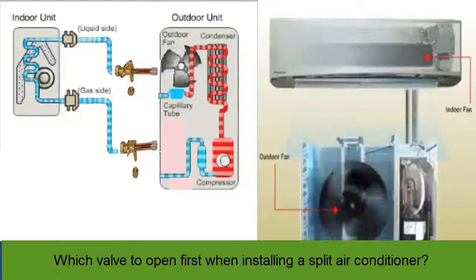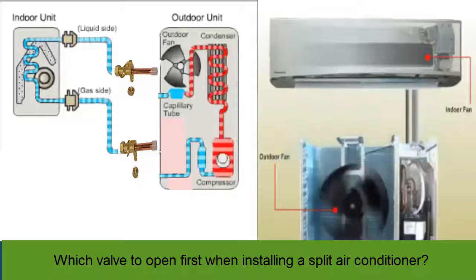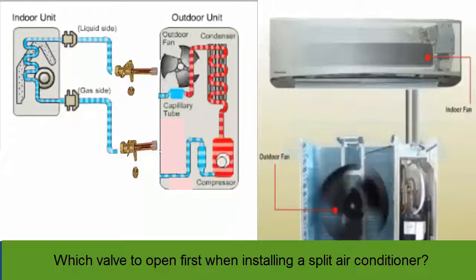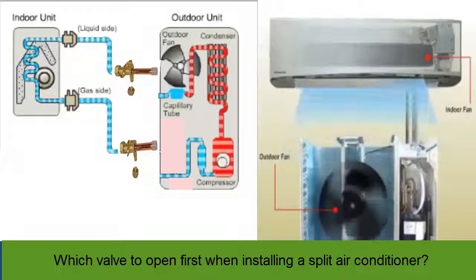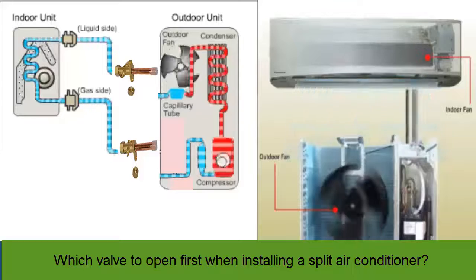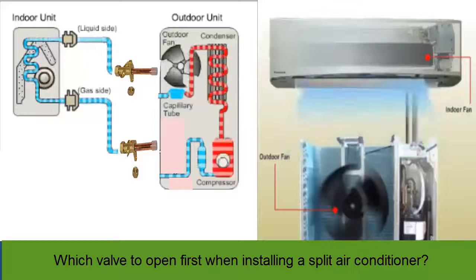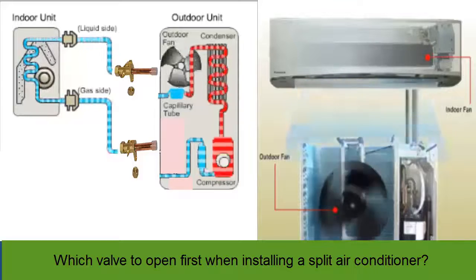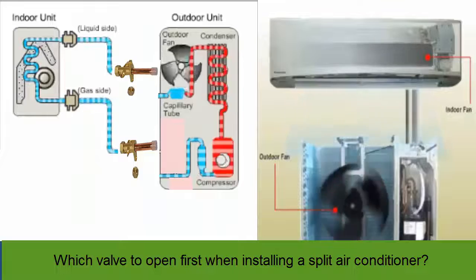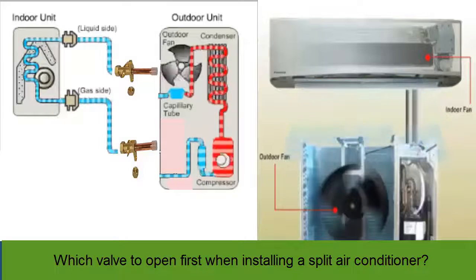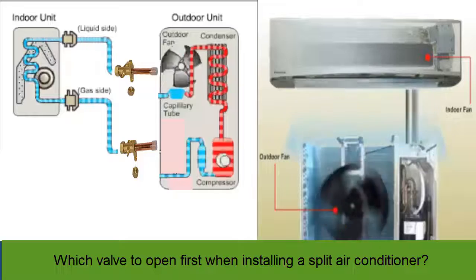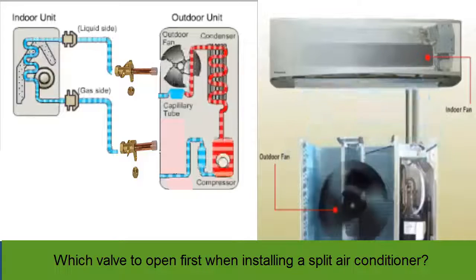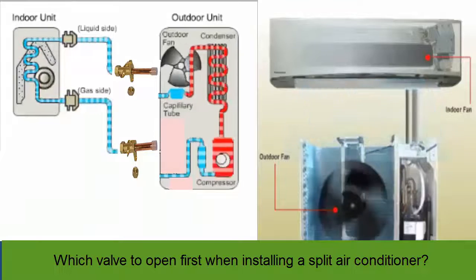When the unit is in operation, both valves are located in low pressure pipes. The thicker valve is located in the pipe that receives gas from the evaporator — a low pressure point at the outlet of the evaporator. The thinner valve is located in the pipe just after the capillary tube, that is after the expansion low pressure point toward the inlet of the evaporator.